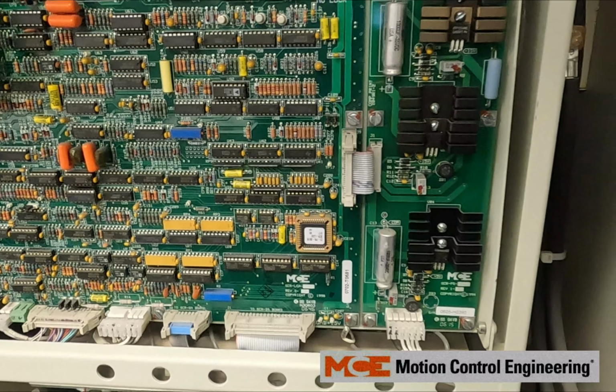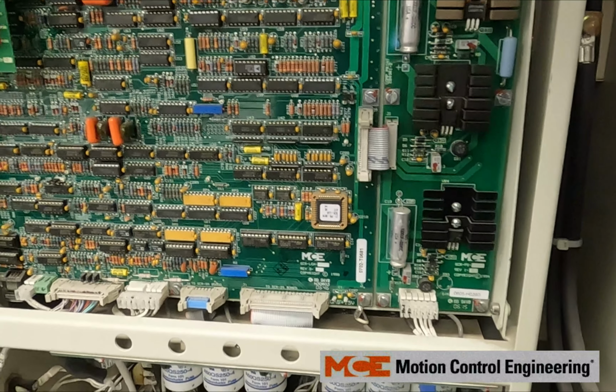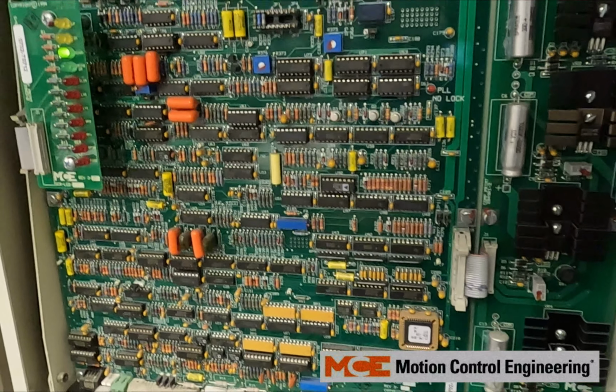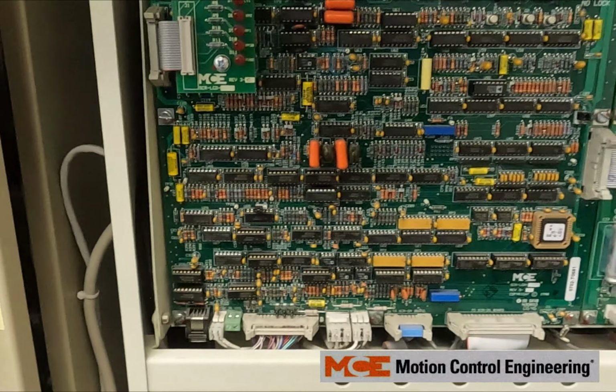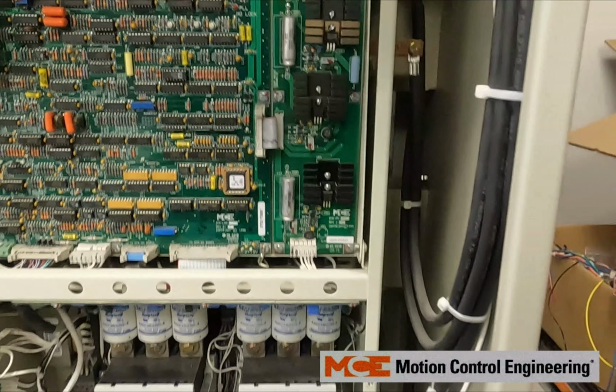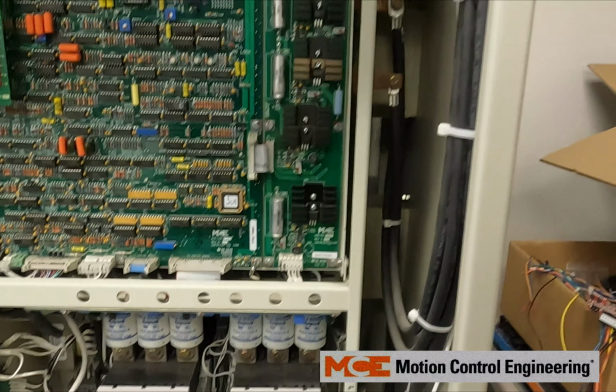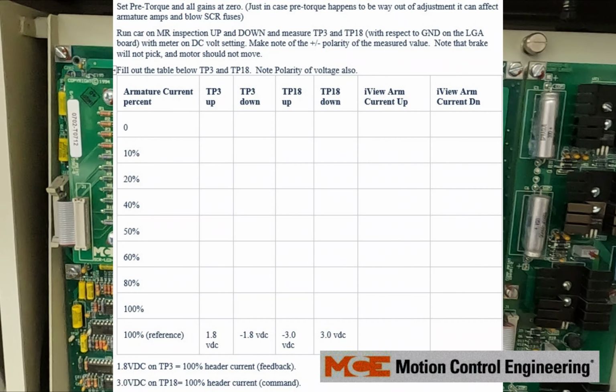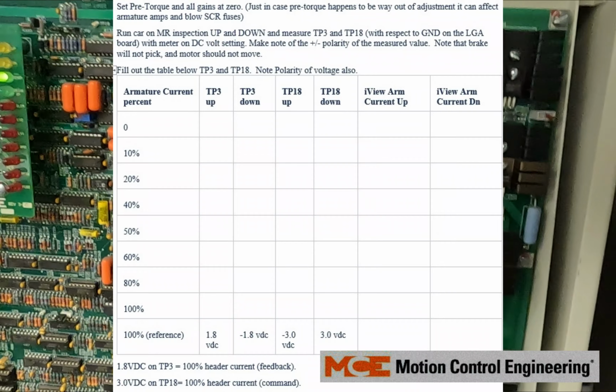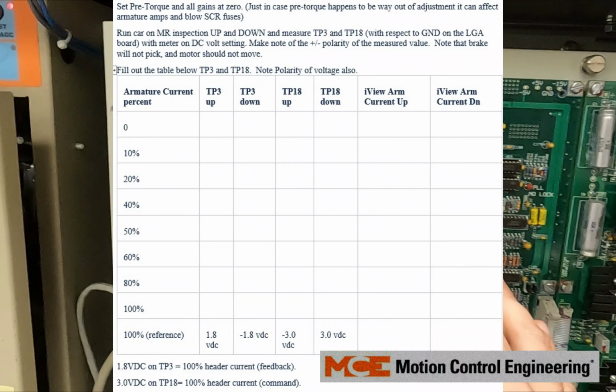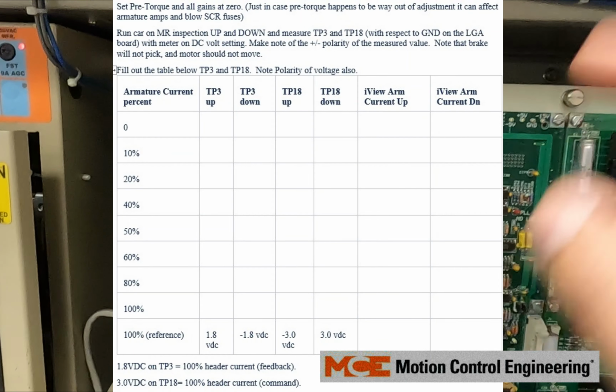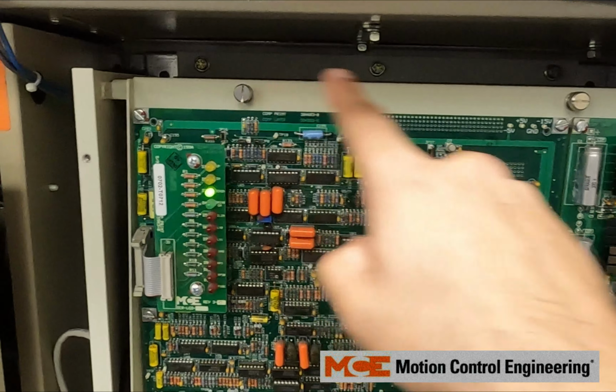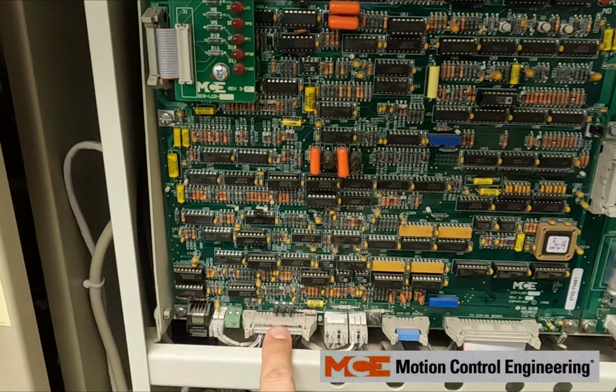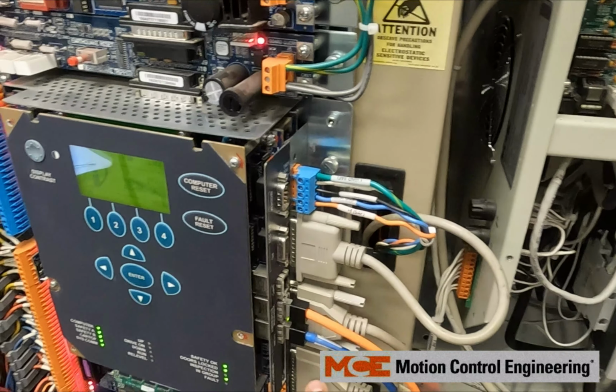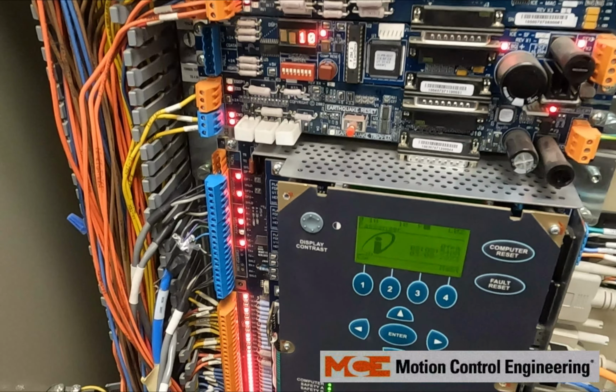If you guys are experiencing an insufficient SCR armature current fault at idle, through the run, intermittently, I'm going to show you guys in the next screen a page on what you'll need to fill out to test your armature current test from 0%, 10%, up to 100%, to make sure all the numbers check out and verify if it's an SCR drive current sensor issue on the DS board behind the LGA board, or it can be the LGA board up to the drive cable, from the drive cable to the right side of the iBox. Ultimately, it could also be an iBox issue.